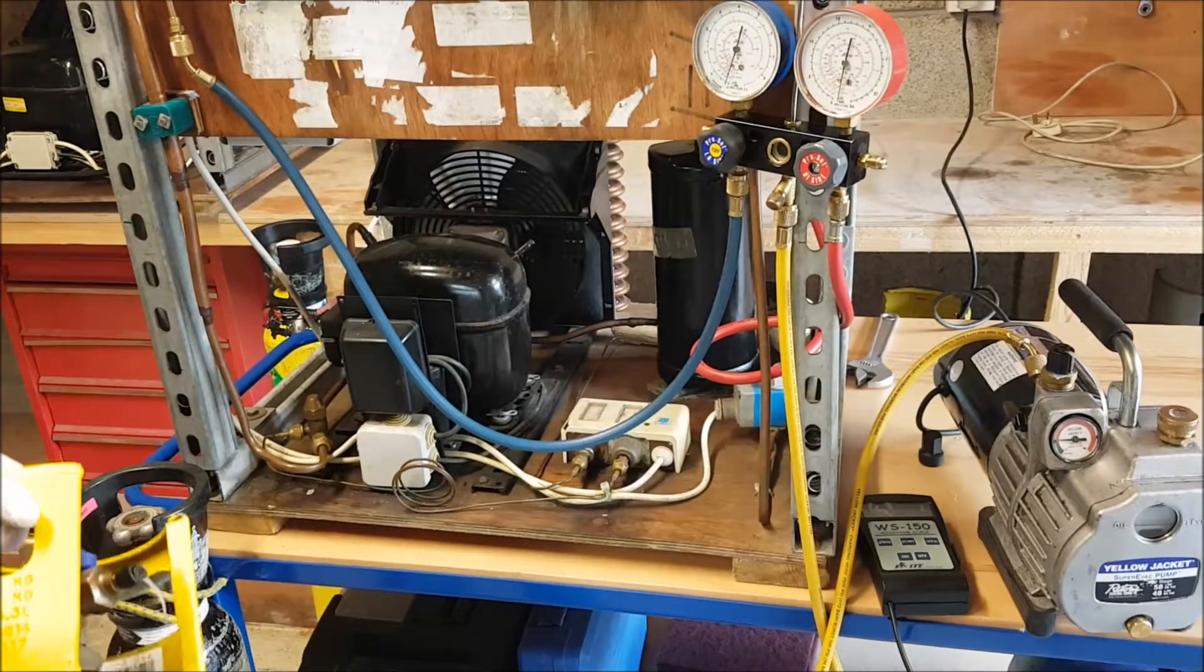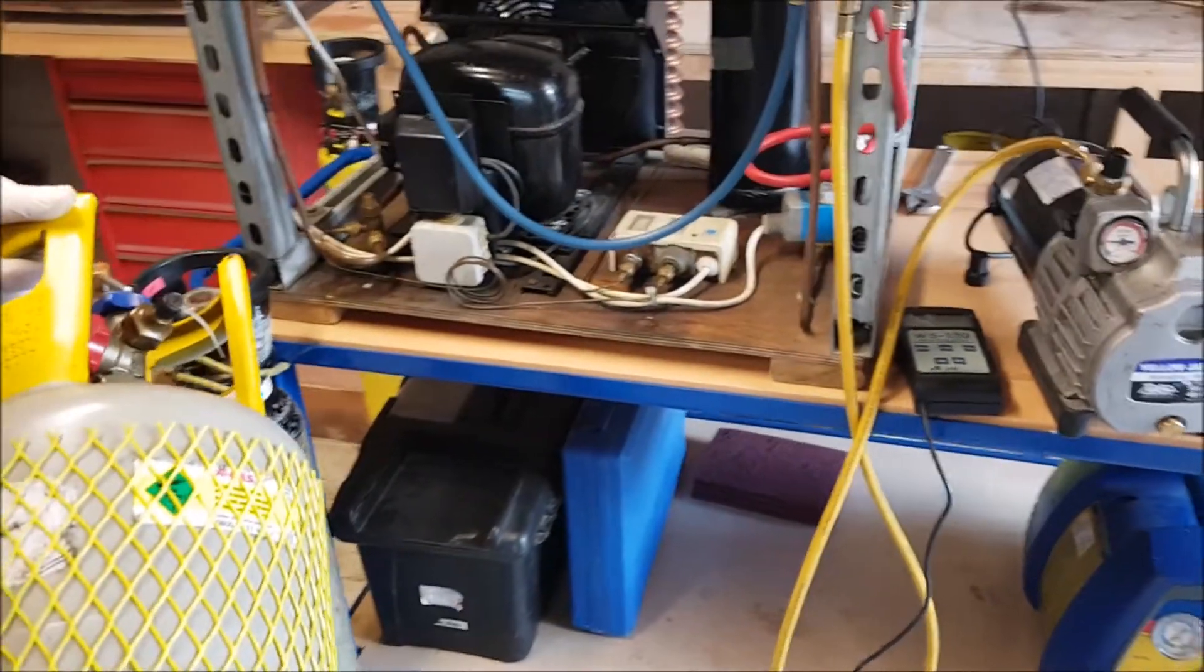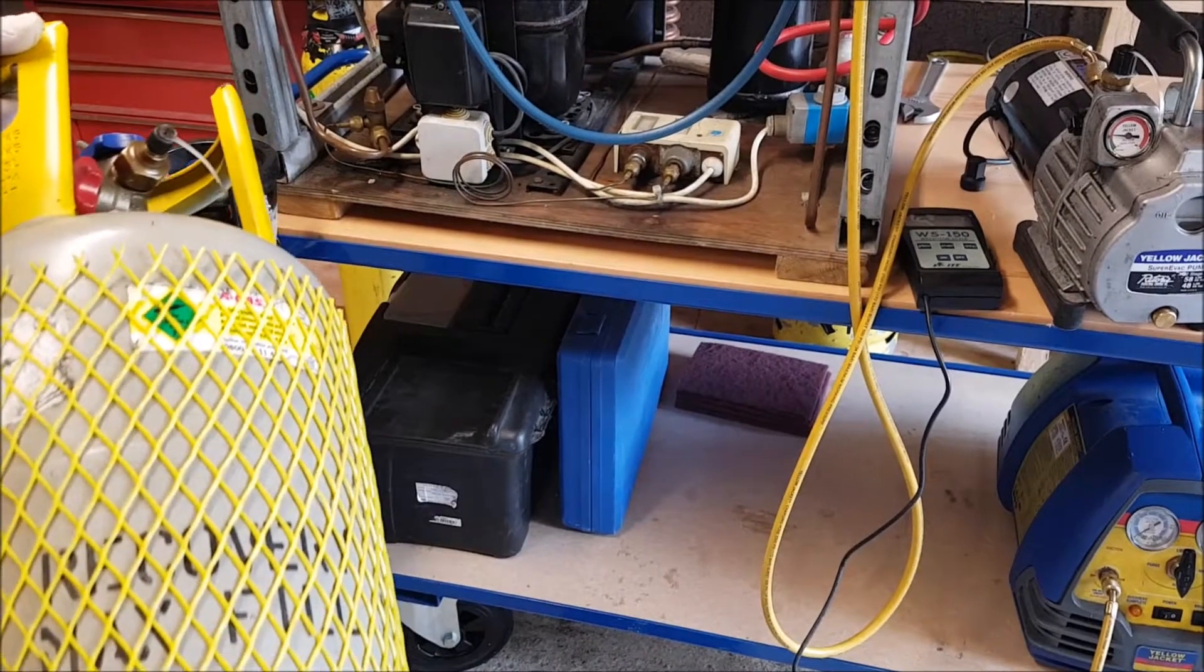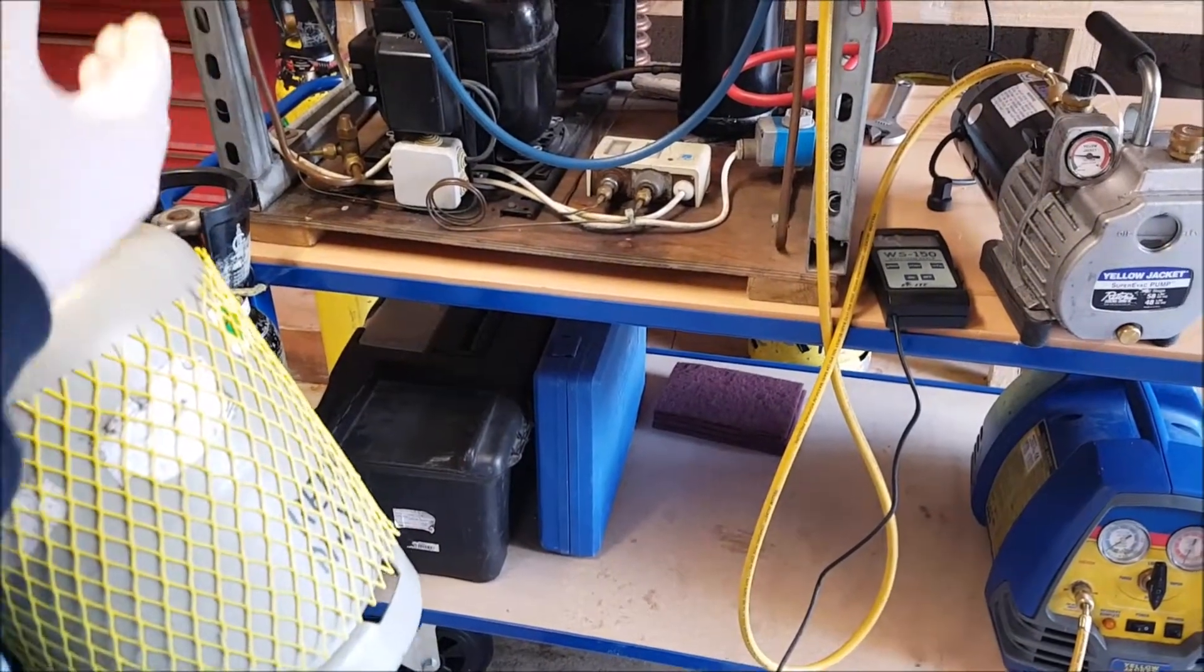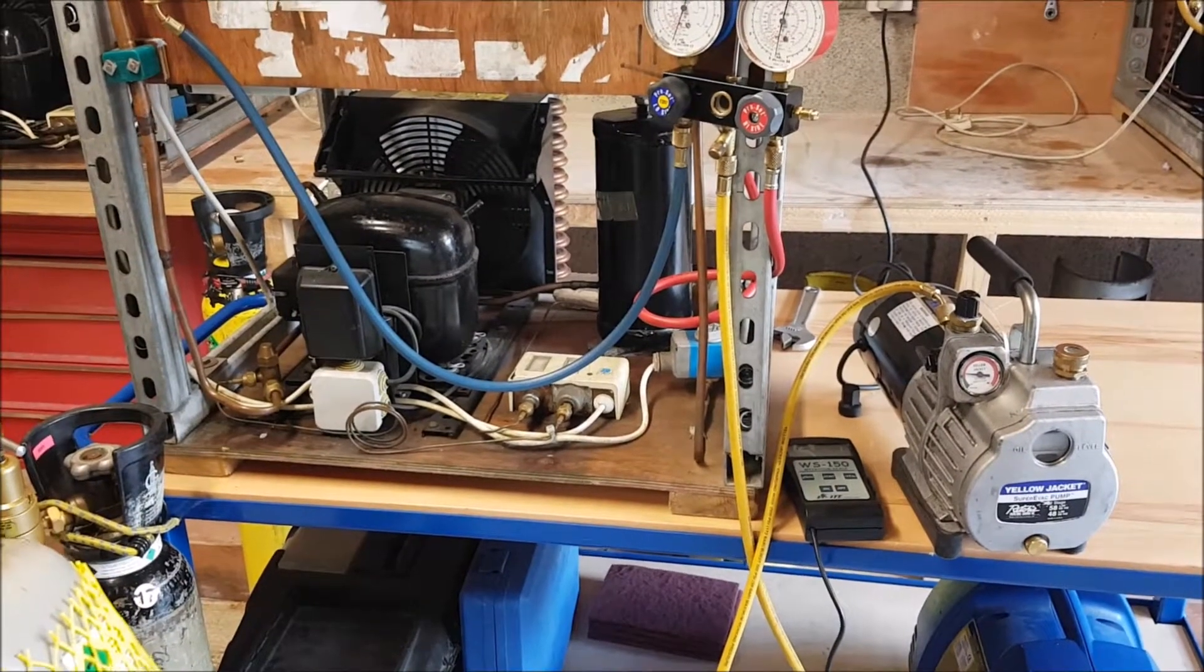We're now going to use our recovery bottle that we'd already recovered refrigerant into. This was labeled as recovered refrigerant and it was labeled as good for reuse. It's basically refrigerant that we had removed from our system while we carried out our remedial repairs, and now we're putting the same refrigerant back into the system.